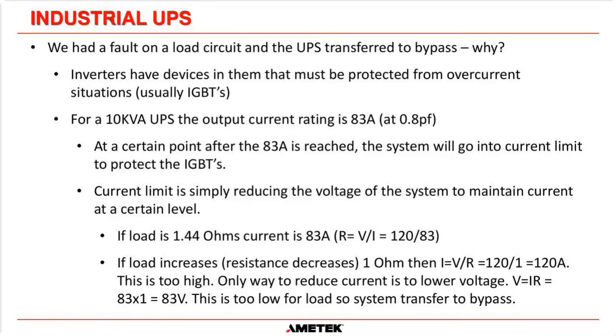When they see high current, they detonate pretty much instantaneously. There is no fuse quick enough to protect an IGBT. So we have to do the current limiting electronically. Current limit is simply, and there's a lot of confusion around current limit, reducing the voltage of a system to maintain current at a certain level. Hopefully this example will give you a better idea of how current limit works.